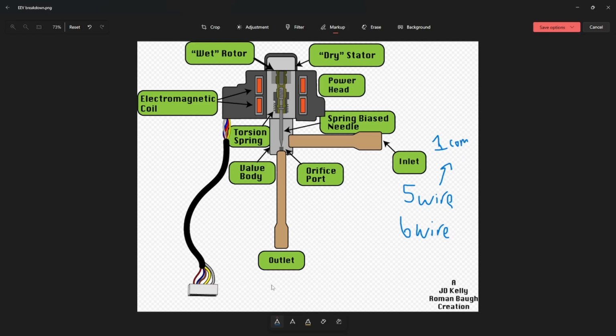The color is going to vary. Sometimes it's gray, sometimes it's blue. You have to refer to your manufacturer literature to determine what the common wire color is going to be. You could also just start checking the wires to each other and see where you get your reading, because only one of those wires will have continuity to the rest of them. That's your common wire. Pretty easy to figure that out just by trial and error.